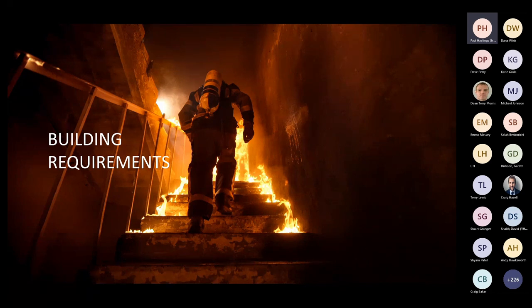We'll now go over the basic building requirements for a firefighting lift, including what we have found being forgotten in the design of new buildings. As an example, we recently undertook a project in London for a two-core apartment building and were called in after the shafts had already been constructed - there was no water ingress protection or raised floors. We tackled the project using our experience with existing buildings and have a full case study on our website.